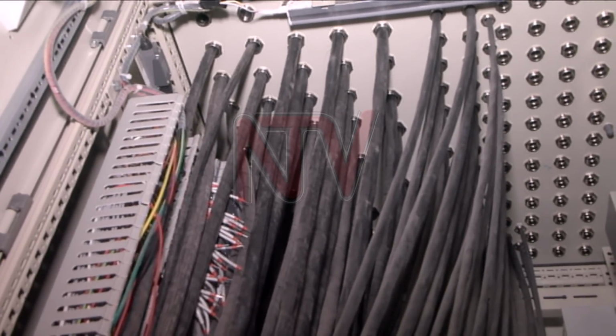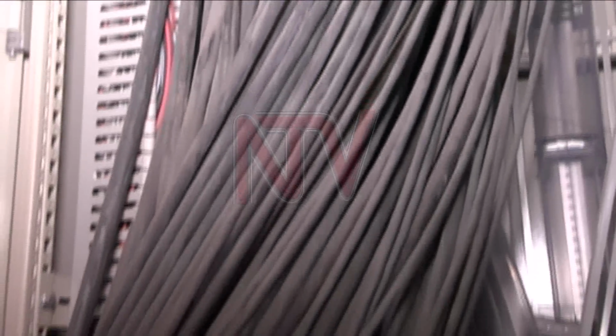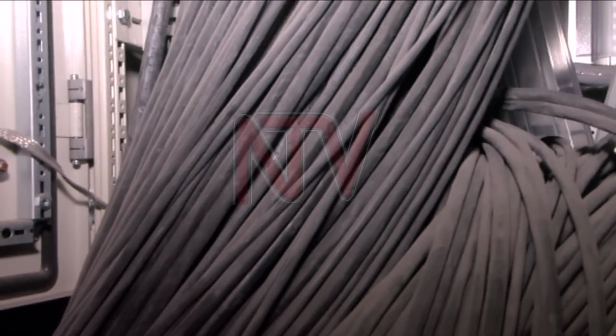So when I came, I found the issue of snags. You know, the cabling, the cracks, and all that. But I'm happy to note that the contractor really tried to work on these snags. The cabling, you could tell the difference. Initially, they were just bundling, and you would wonder if one had an incident of fire, which cable to deal with. But they were all well aligned, and some other defects were being worked on.